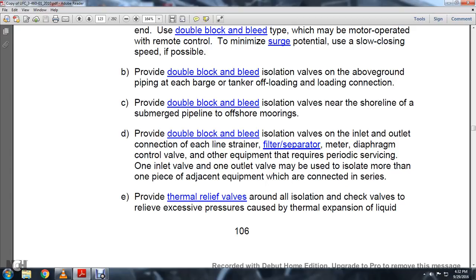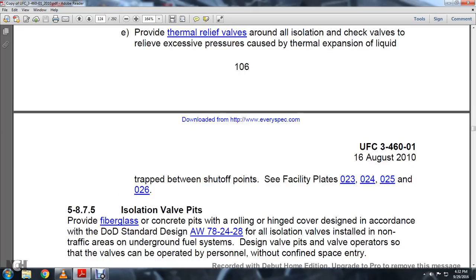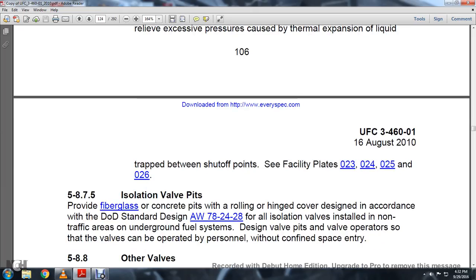One inlet valve and one outlet valve may be used to isolate more than one piece of adjacent equipment connected in series. Provide thermal reliefs around all isolation check valves to relieve the excessive pressures caused by thermal expansion of liquid trapped between shutoff points. See facility plates 023, 024, 025 and 026.